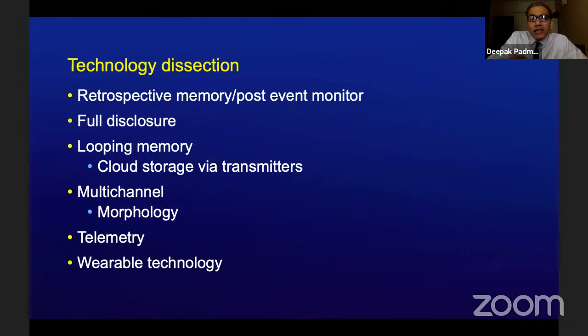The device can record ECGs either as a single channel ECG or a multi-channel ECG. The multi-channel ECG can be a 3-channel, 6-channel, or 12 channels also. If you are doing anything with respect to ventricular arrhythmias, it is usually preferable to use a multi-channel ECG. You do not want to use a single channel ECG for ventricular events, because although it will tell you that the events are there, further on when you send the patient to an electrophysiologist or a cardiologist for further evaluation, they may have to repeat it to understand where that particular ventricular event is coming from.